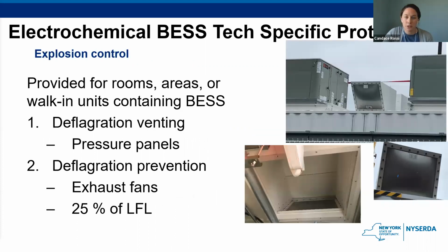So here we have the explosion control requirement that's necessary for all battery types. Explosion control can be handled in 2 ways. We have deflagration venting, which utilizes pressure panels. If there's enough built up gas pressure in the unit, it will push open the panels and release the gas. Most lithium ion systems will have deflagration venting panels that will manage the overpressure blast wave that is produced in an explosion. That blast wave will be sent through the venting panels and should maintain the integrity of the container. These panels' venting direction should also be directed to an area that won't interfere with the fire department's operations. So you can see an example of this on your screen.